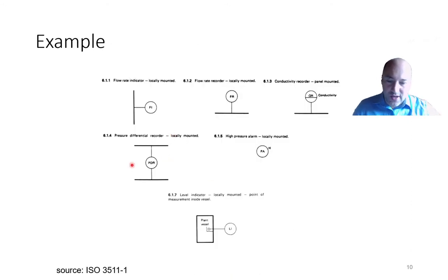So here are a few examples. Those examples are taken directly from the standard that I'm talking about. You can see the symbol here, with this thick line. This is telling me that it's the material flowing. So the PI diagram is like a block diagram where you have individual blocks or individual tanks, for example, and you show the flow of materials in this diagram with those thick lines. And this thin line is telling me that I measure the variable and this is my instrument.